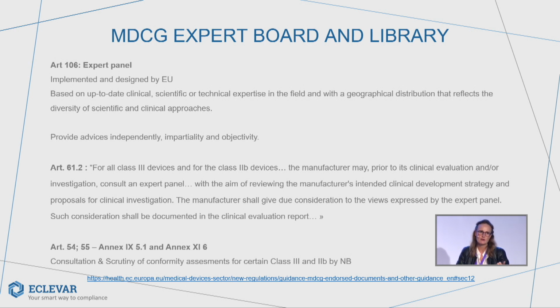The first level is that manufacturers of class 3 or class 2b medical devices can request the expert panel advice prior to collecting clinical evidence. So this is just asking for an opinion. Could you help me in my strategy? What should I focus on?